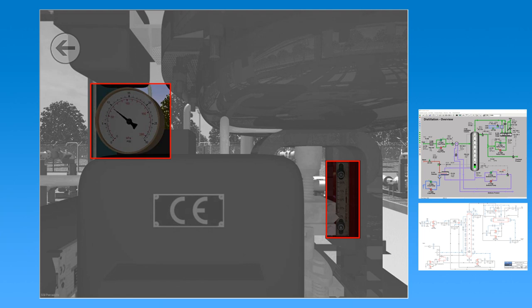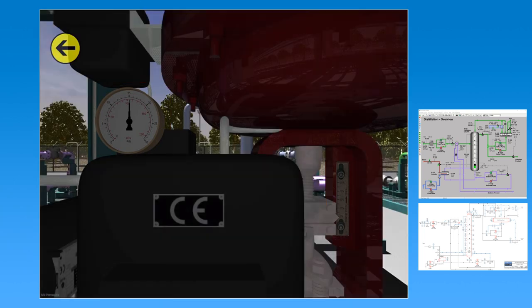The console operator switches the controller to manual and changes the controller's output, which shows the gauge changing but does not show a change on the stem. The preliminary conclusion is that the valve has failed closed and is the cause of the problem.